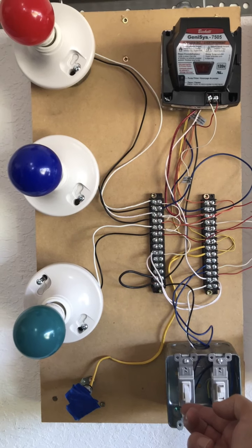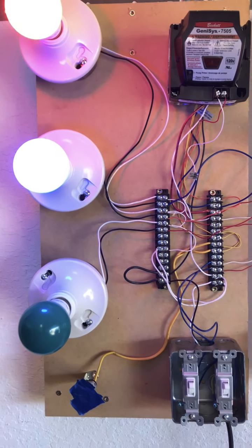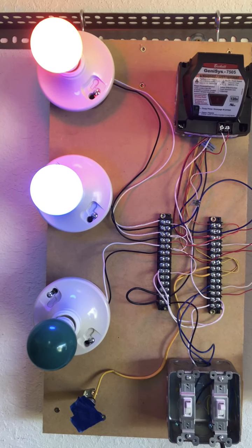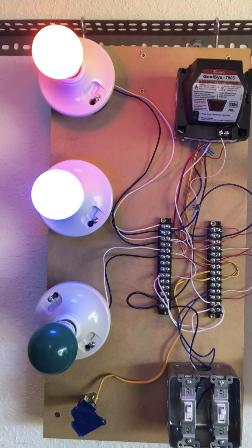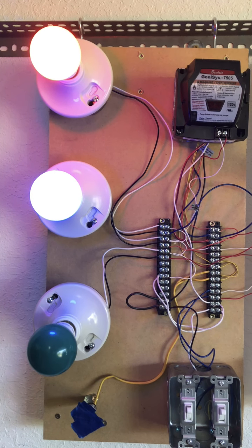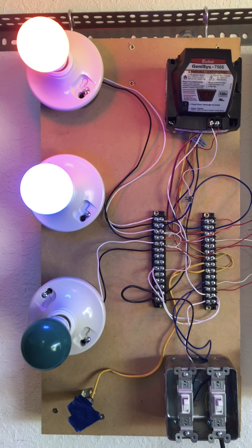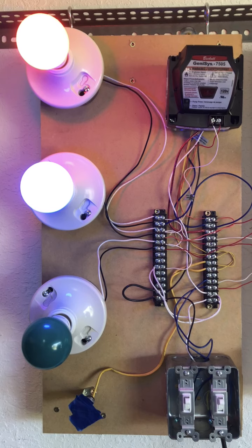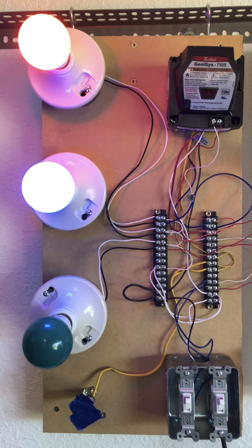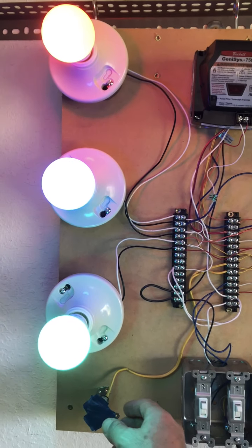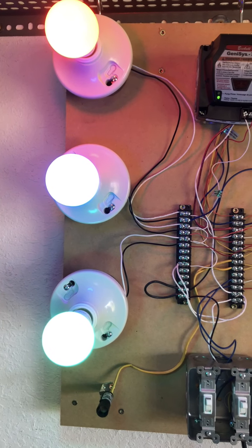I come in here, my thermostat's calling, my burner motor comes on, my igniter comes on. We're waiting for the solenoid. Again, this is a timing. We want the solenoid to open. My pump's spinning, I have oil pressure. My solenoid opens. I now should have flame in the chamber.